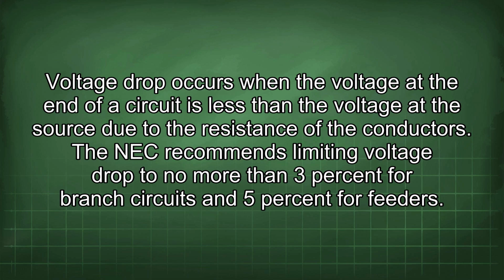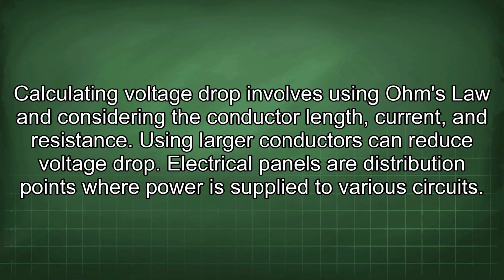The NEC recommends limiting voltage drop to no more than 3% for branch circuits and 5% for feeders. Calculating voltage drop involves using Ohm's law and considering the conductor length, current, and resistance. Using larger conductors can reduce voltage drop.